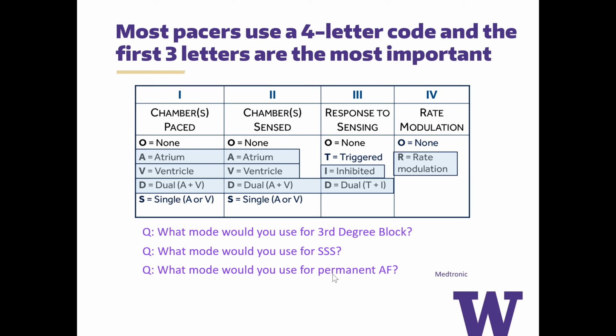In patients with permanent AFib, the reason that they most commonly need a pacemaker is, for instance, if you want to rate control them. And you're limited in rate control because if you put them on too much rate controlling agents, they can have periods when they get really bradycardic. And so, classically, those patients are called tachybrady syndrome patients. And so the reason they would be getting a pacemaker is because you want to have some kind of backup pacing in place. And so at the very minimum, in patients with permanent AFib, they should have the ventricle being able to pace. So that first letter needs to be a V.